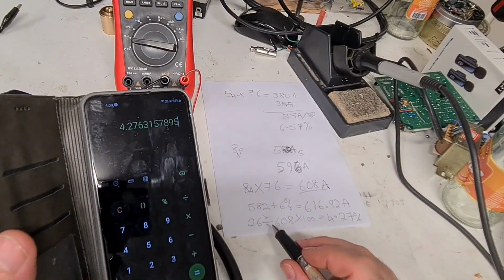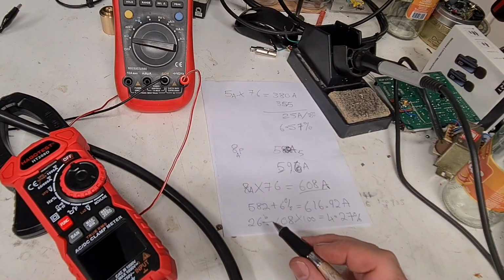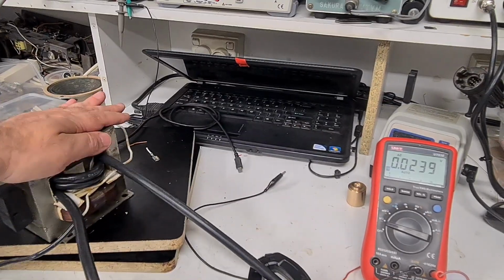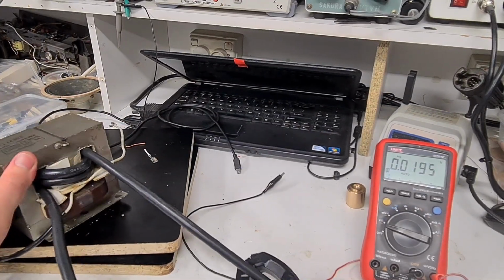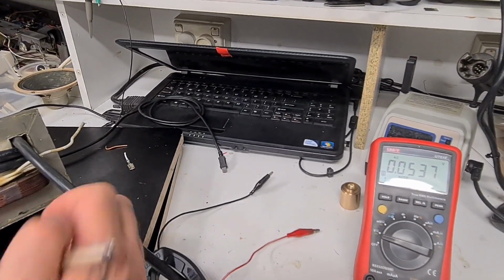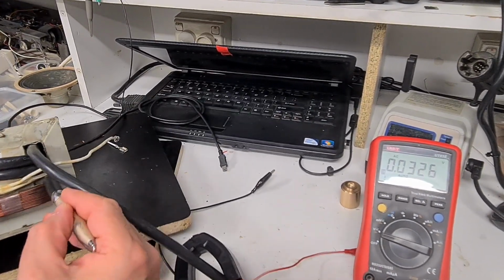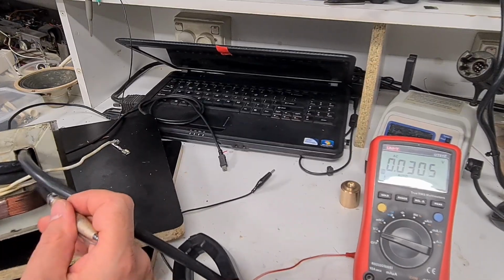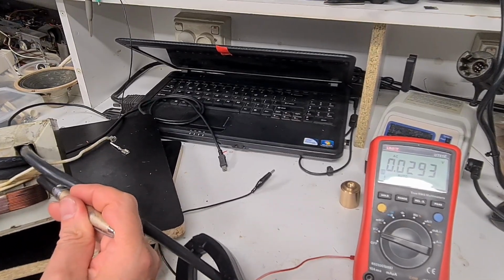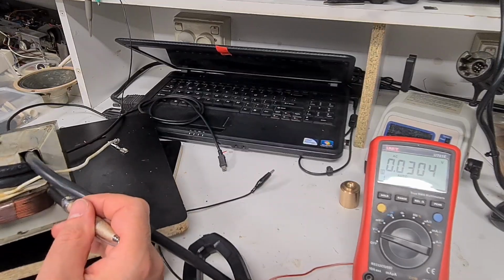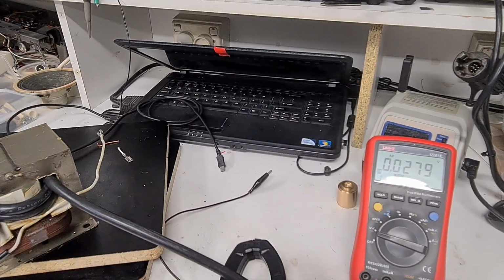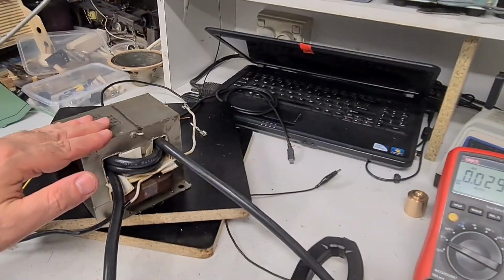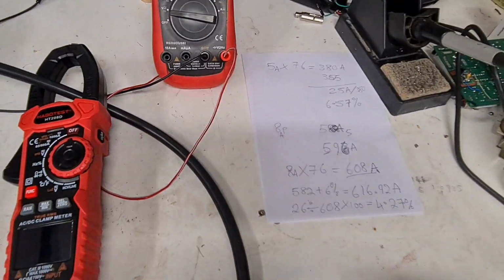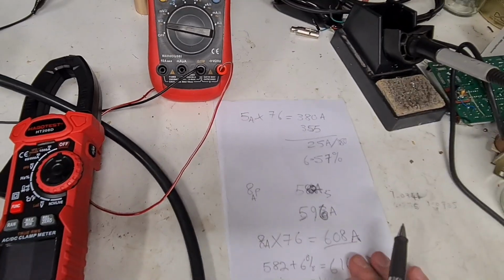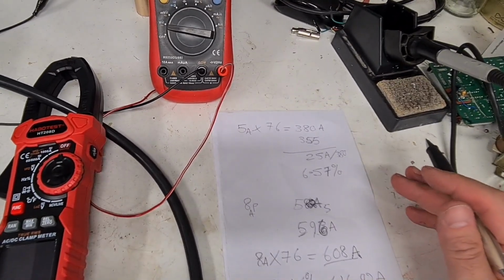So you see, I read 582 and I should have read 608, which is only 26 amps less. Therefore, like I said, I don't believe I need to remove the shunts. The reason is I'm going to use this transformer, and I don't like disturbing anything on the primary, because these shunts are epoxied in there, and there's not much insulation between the shunt and the primary. So, not to wreck the job, I think this is going to do fine for what I want to use it for. But I still want to prove the point that the information may depend on some transformers.